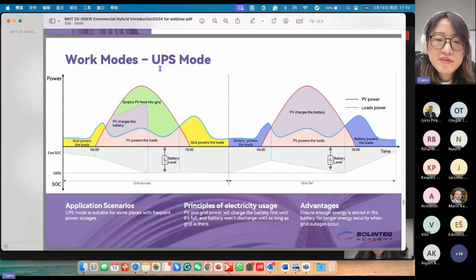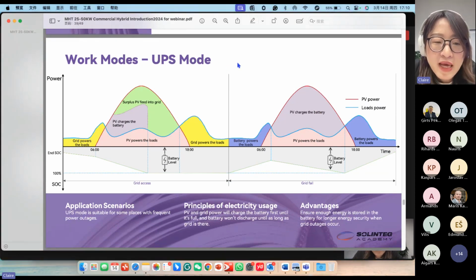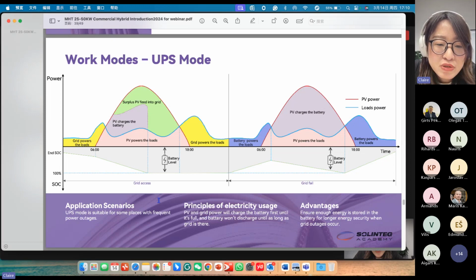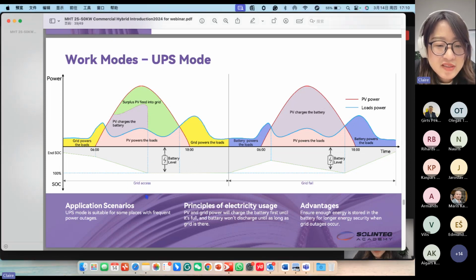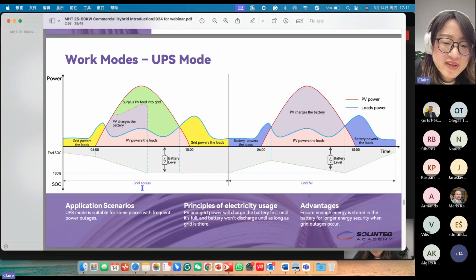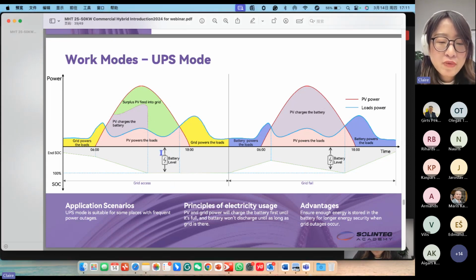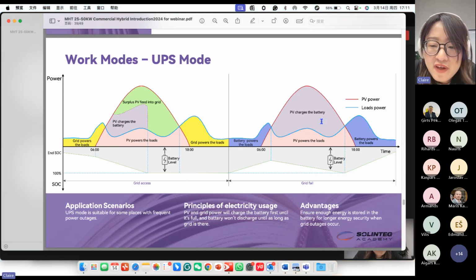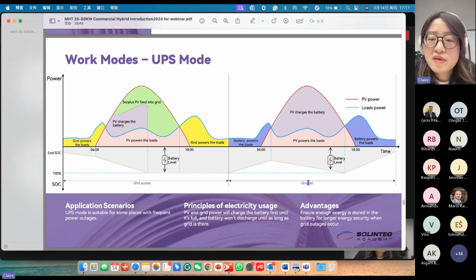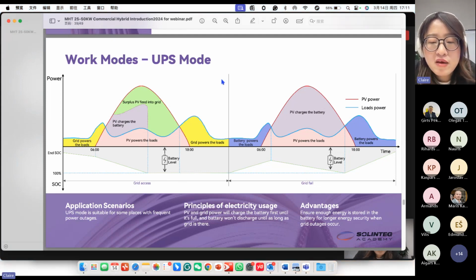And this is the UPS mode, which is usually used in countries that always have power blackout problems. For countries that don't have this problem, I don't suggest using the UPS mode, because in the UPS mode, the battery won't discharge as long as the grid is connected. So when your system is first started, the battery will be quickly charged to full, and it will never discharge if the grid is connected. But when the grid fails, the battery will discharge to supply the loads together with PV. So this one is usually used in places like South Africa or other African countries. They don't have stable grid supply.